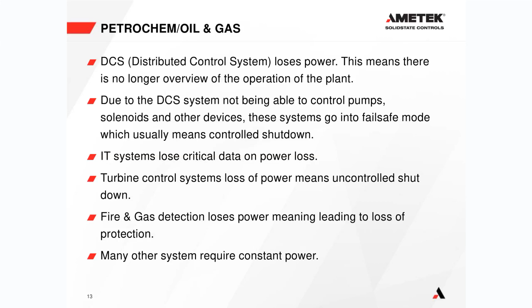On turbine control systems, a loss of power means an uncontrolled shutdown of turbines. On fire and gas detection systems, losing power means a loss of fire and gas protection, and that usually means everything shuts down because that system is no longer operating. There are many other systems in a petrochemical or oil and gas situation where constant power is required - meaning you can't have even a second's worth of power loss. The power has to be continuous at all times.